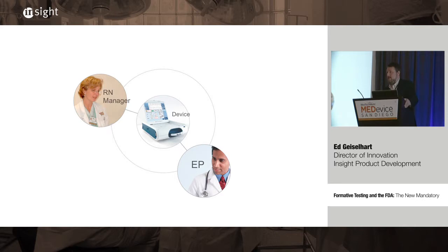When we talk about a user, it's very, very critical to be mindful of the potentially diverse, distinct user populations that might utilize your medical device. In the case of a pacemaker programmer, which is in the middle here, you might consider yourself to be doing a pretty thorough job of canvassing your user population if you talk to an implanting physician. And if this is all you talk to relative to developing your device, you're talking to about 4% of your user population. You really need to be talking to nurses as well. They really constitute about 80% of the use of this device.